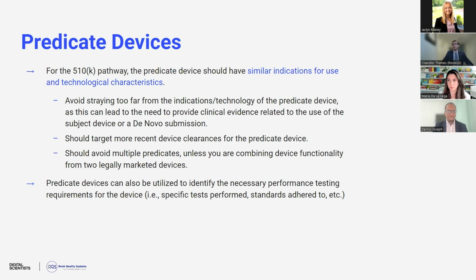So as part of this, you want to avoid straying too far from the indications and technology of the predicate device. Otherwise, you might need to provide clinical evidence related to the use of the subject device, or you might put yourself in a new product classification and be subject to the de novo submission pathway.